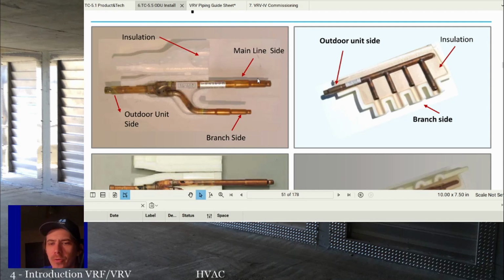In general, what I get told in these installation classes, no matter what manufacturer I'm dealing with, is their rule: if you've got the proper Y kit and you need to connect these two pipes, connect those two pipes basically by any means necessary. So, just because this gets bigger and then smaller is no big deal. Just shove the pipe in and you're good. If you need to go to an even bigger pipe than what you have here, then you'll cut this pipe, put on a backwards reducer, and make the pipe bigger after it. It doesn't matter. In general, I never recommend doing that unless you're working on VRF. For the most part, you want refrigerant pipe to stay the same size the whole length from indoor to outdoor with single reducers at that exact point.